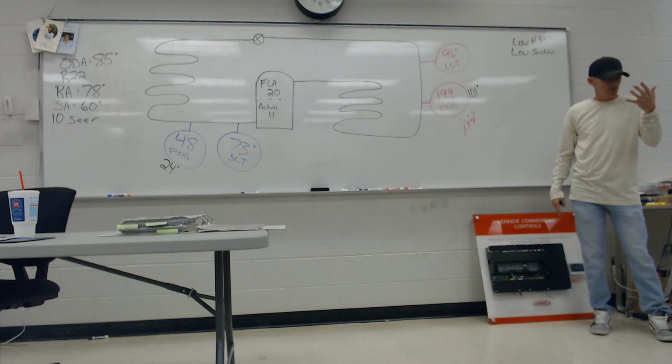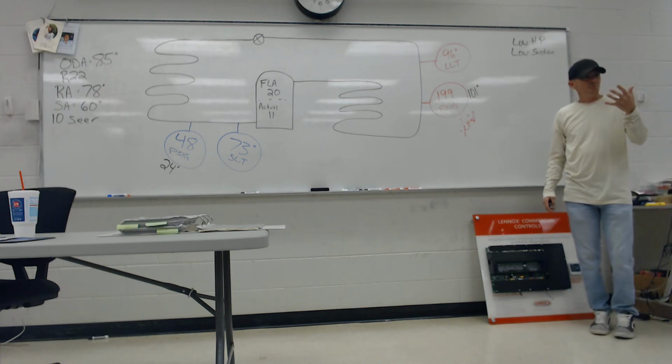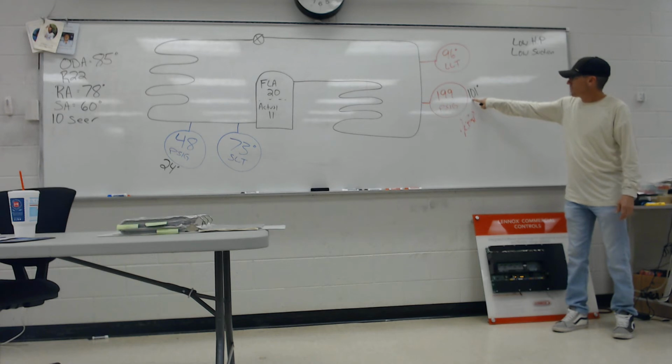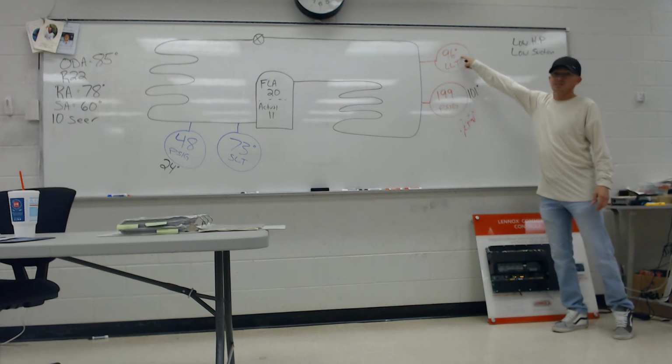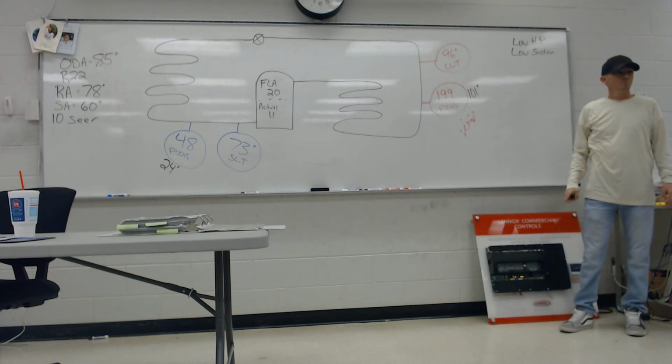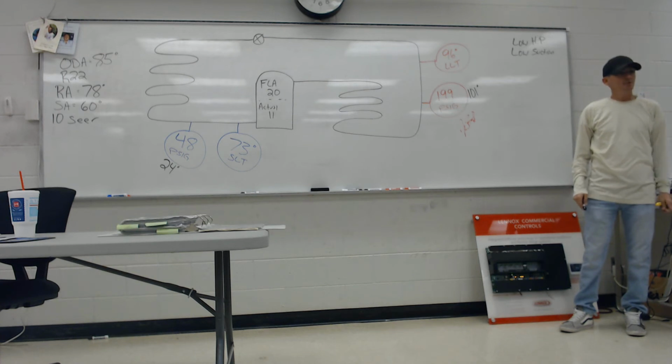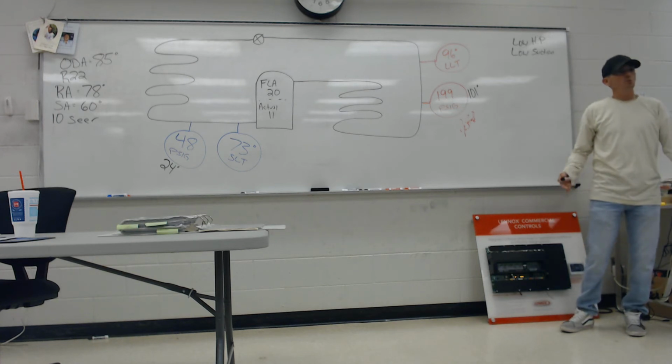It's an R22 machine, so I look at the green numbers. I got 101. It condensed at 101, and then I subcooled it down to 96. That's 5 degrees of subcooling. What should I have, roughly? 8, 12. So what do you want to say about the subcooling?